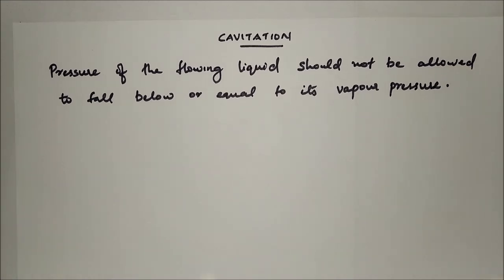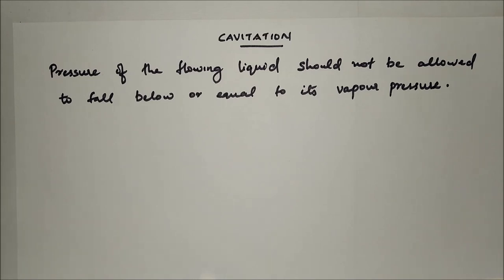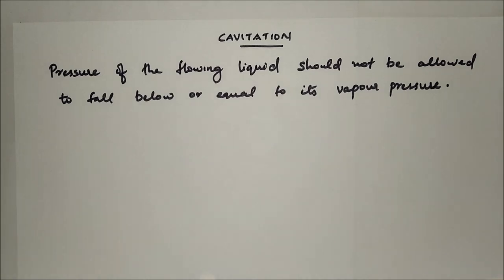In reaction turbines, cavitation occurs at the outlet of the runner or at the inlet of the draft tube, where the pressure is considerably reduced. Due to cavitation, the metal of the runner and draft tube is gradually eaten away, which results in lowering the efficiency of the turbine. There will be a sudden drop in efficiency due to cavitation in case of reaction turbines.